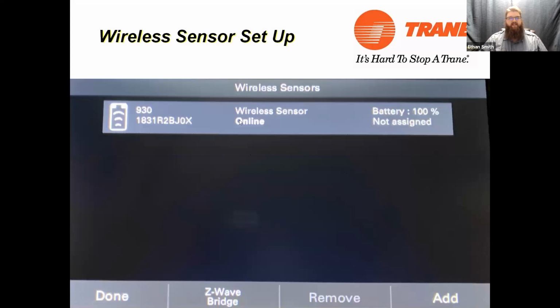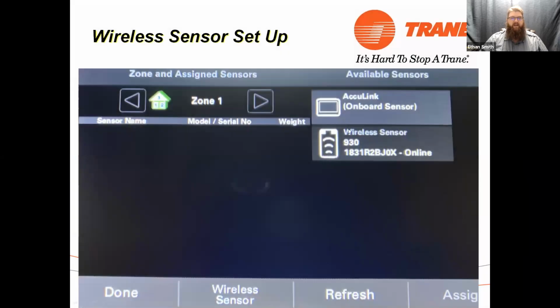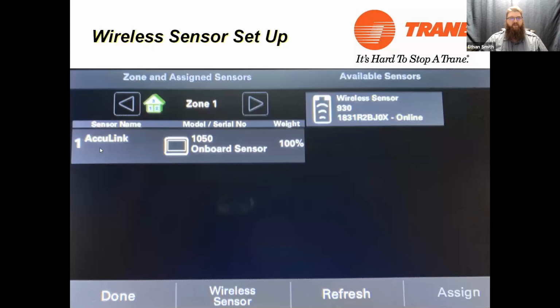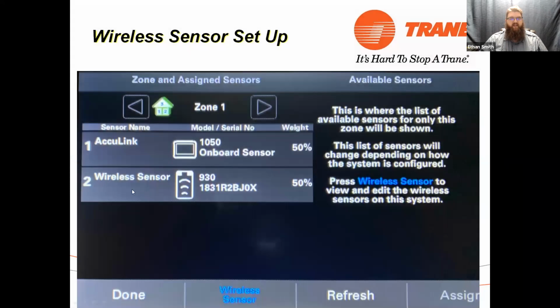So once you push those buttons, it will show up as a wireless sensor that's online. It will say not assigned. Okay. And it will show up in any zone as an option. So we want to use it for our zone 1. We're going to select that wireless sensor and hit assign. It will then say we've got our 1050 onboard sensor. Once we assign the 930, it will say the 1050 and the 930. And you'll notice that the weight is 50% on each of them. So it's going to average between these two sensors.